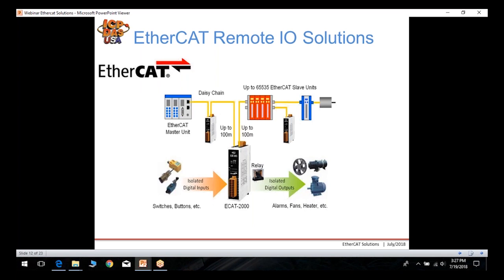This shows the traditional topology for EtherCAT remote I/O. The EtherCAT master is daisy chained to one or many EtherCAT remote I/O modules. You connect your digital and analog input signals to each remote I/O module in the daisy chain, and between each link you can have up to 100 meters in length.